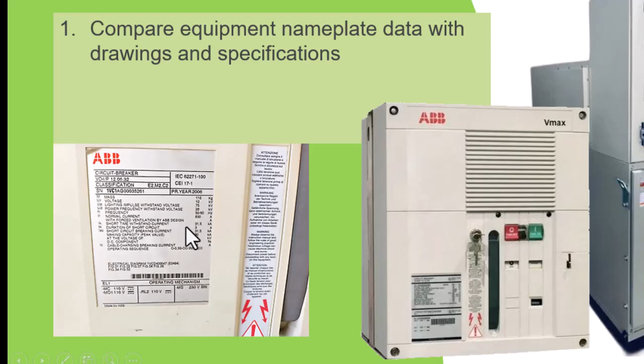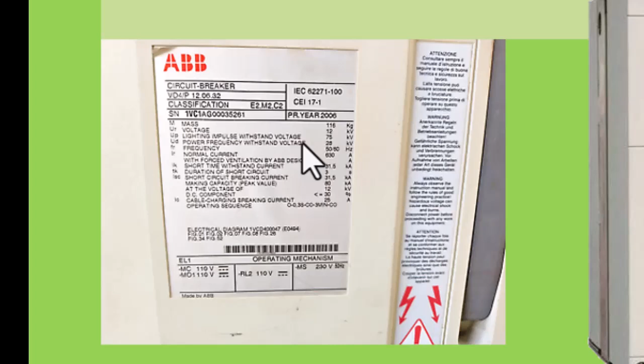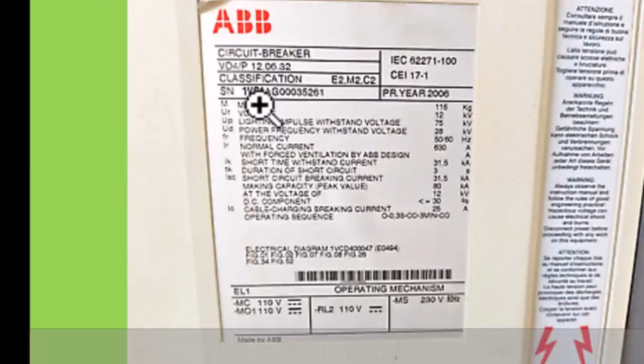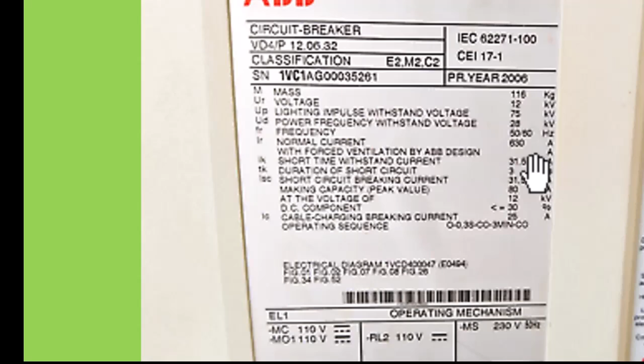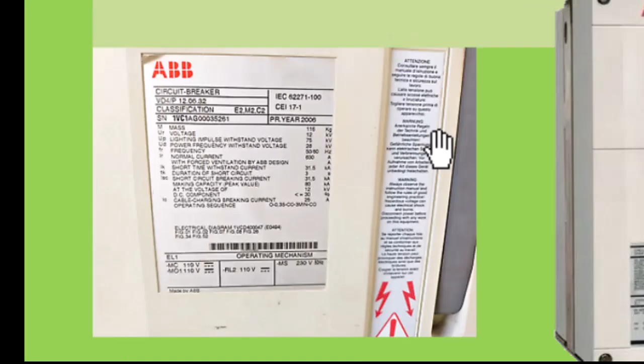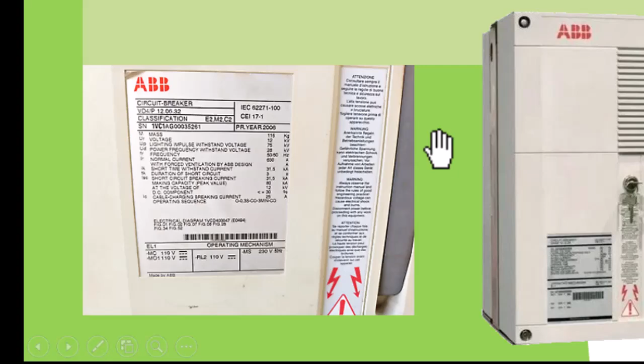You look at the nameplate information and see that it is what we actually expect in that section of the circuit. You can see the voltage, this is 12 kV, and the current, the nominal current rating, which is about 630 amps. We want to check all of this to see that what is actually specified for that part of the circuit is what we have in the circuit.